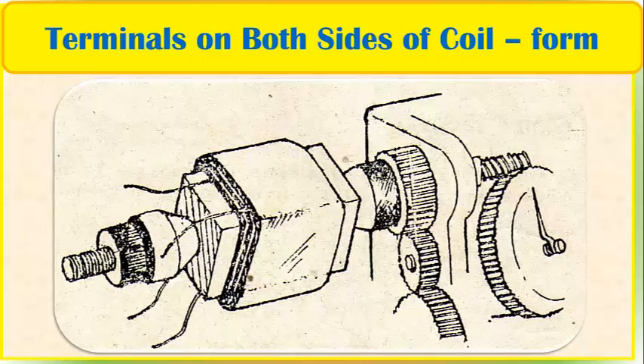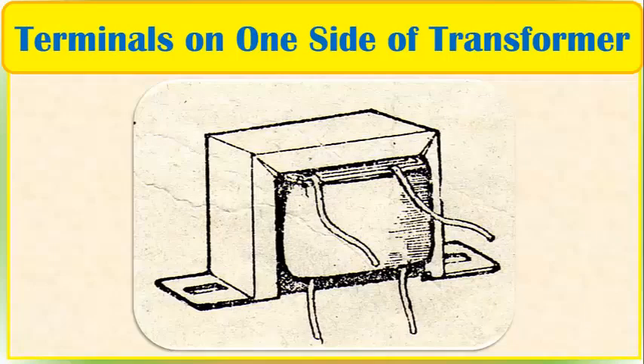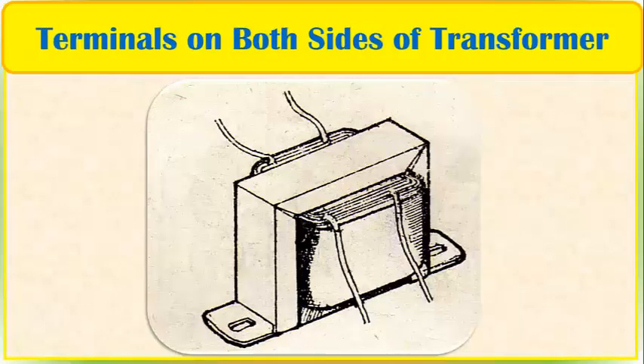The coil terminals. The location of the transformer terminals depends on how you place them on the bobbin. This applies to small and large transformers. Terminals can be either on both sides of the iron core or one side only. Completed transformers correspond to the different placement of terminals and the coil form described earlier. Usually, every pair of coil terminals is placed together close to each other. The primary coil terminals are commonly placed on one side and the secondary on the other side.